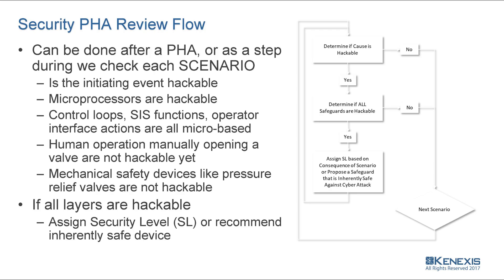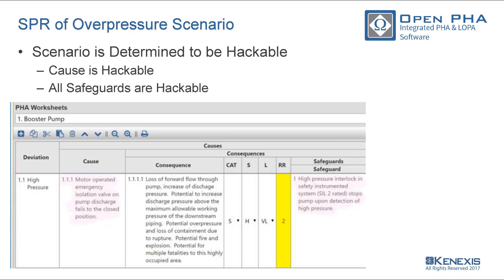There are things that are not hackable, like mechanical devices and human operations. There's some research going on now in using operator interfaces to trick people into doing things they shouldn't, but for the sake of this discussion, let's say that people are not hackable. If you go through this process and the cause is hackable and all of the safeguards are also hackable, that's bad — we have to do something about that. In the pump station case, closing the isolation valve is done by the DCS, so it's hackable, and the one safeguard — the high-pressure interlock — is also hackable. This is no good; we need to do something about it.